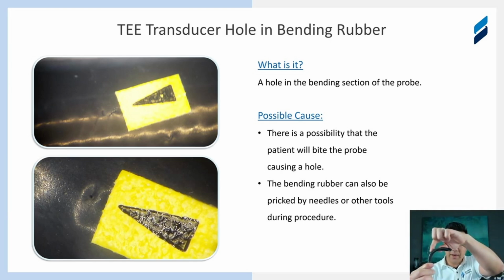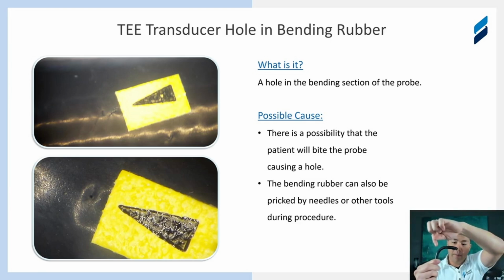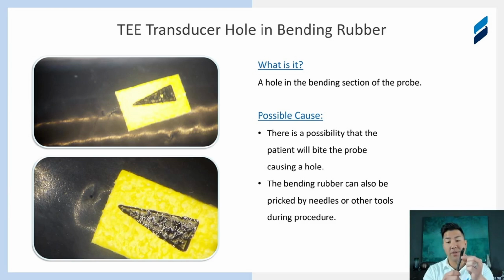If the hole was over here, it may be stretched out and it could be exposed more. But if there was a hole on the outside edge here during a procedure, and now you straighten it back out, that puncture was just pushed back together. And when you put the probe into a leakage tester straight like this, that hole is now sealed by virtue of just straightening the tip.